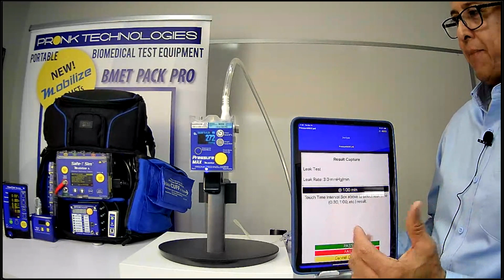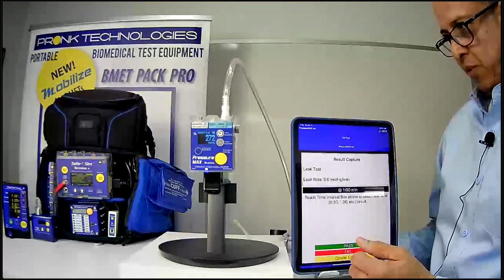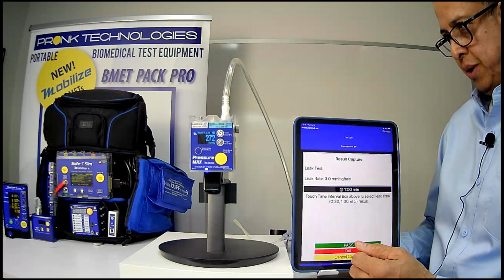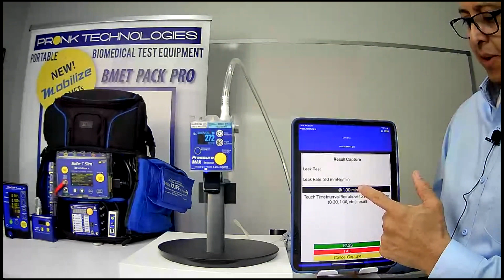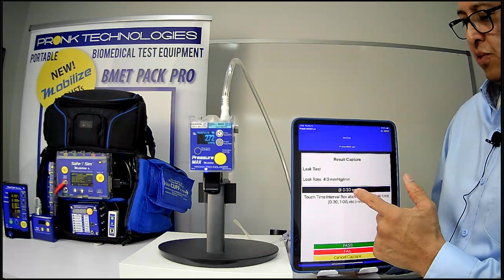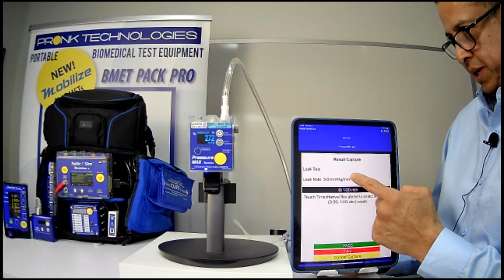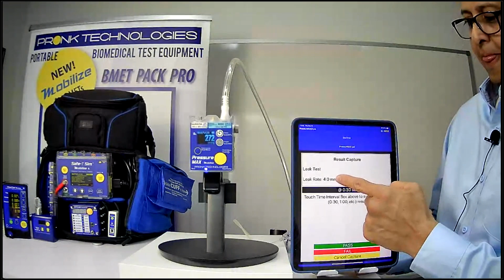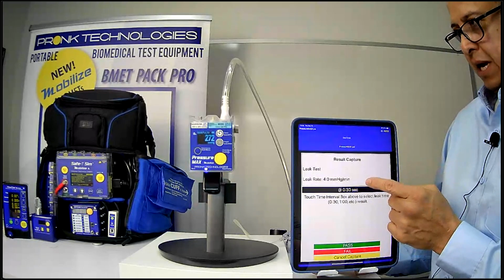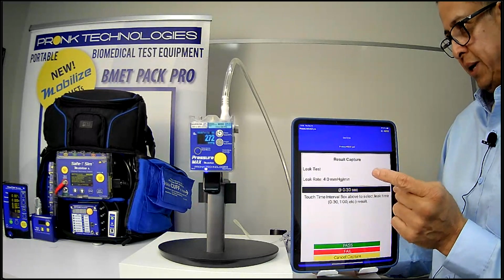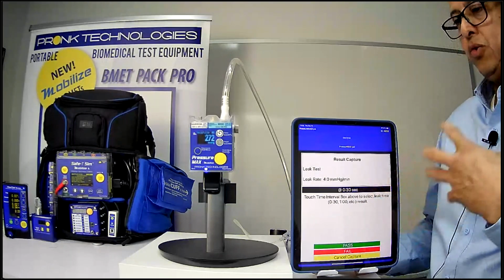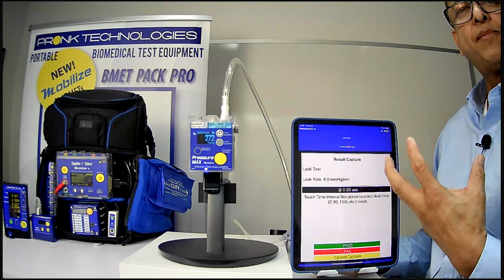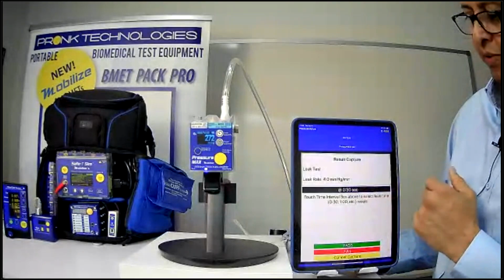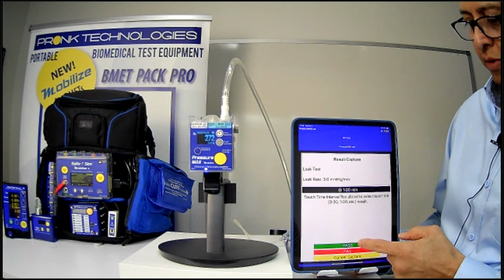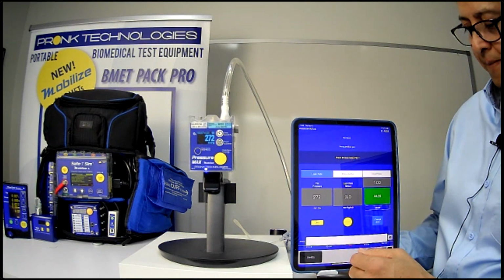Let's say you didn't want to capture the result at the 1 minute mark, you needed to capture it sooner, then you could tap on the black bar here and it will change the interval at which it displays the results, and you could capture that result. You could keep tapping it and toggle between 30 seconds, 1 minute, 1 minute and a half, 2 minutes. You decide the interval you want to capture that pressure at and capture it into the report. So we're going to capture the 1 minute result, and it's all on there.